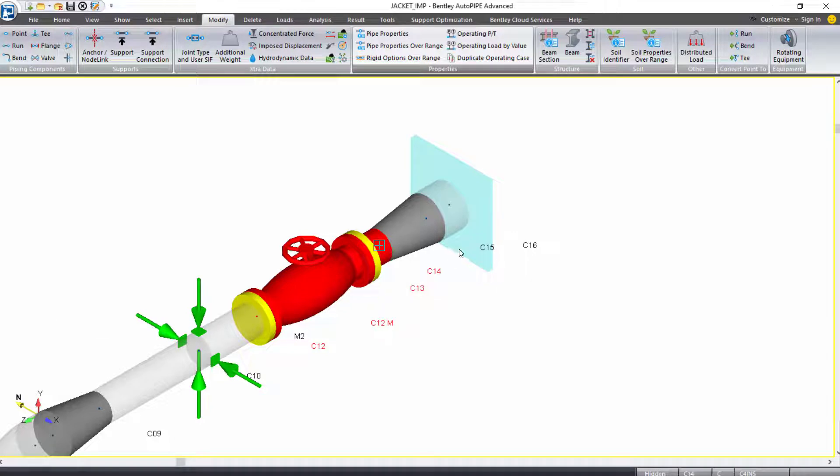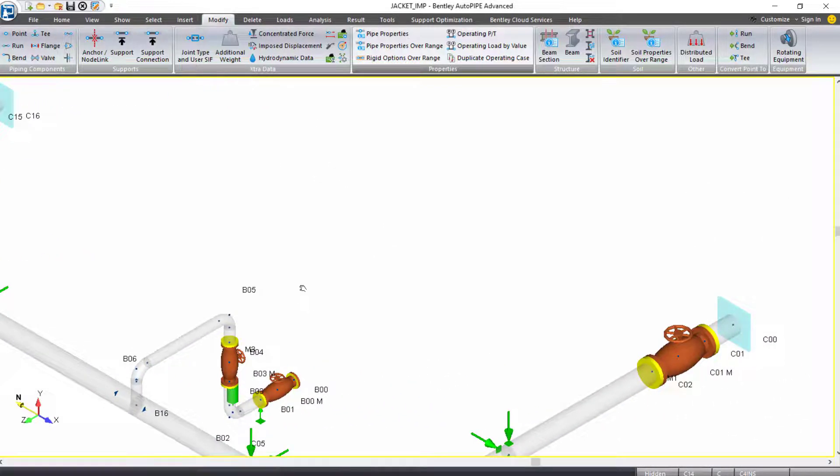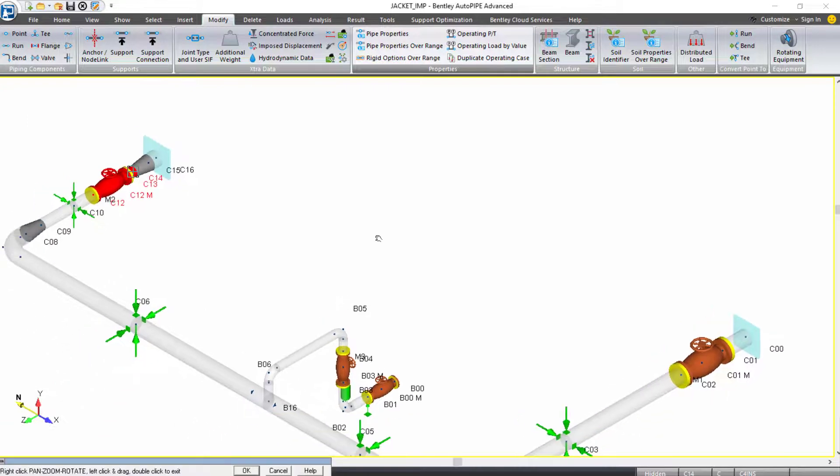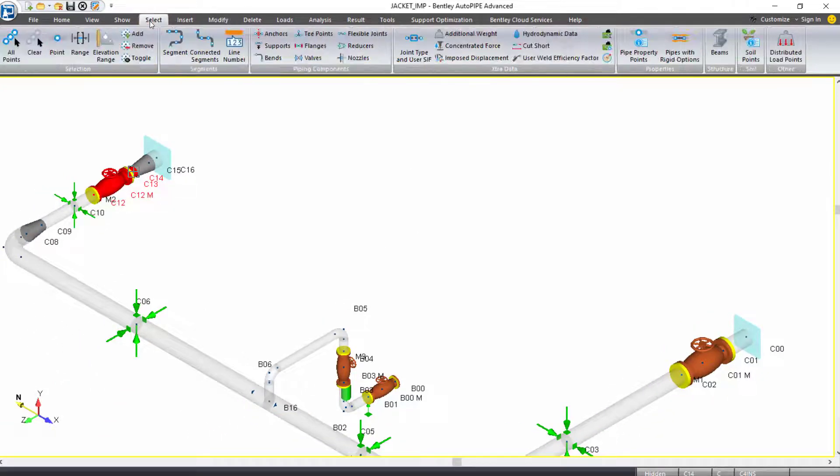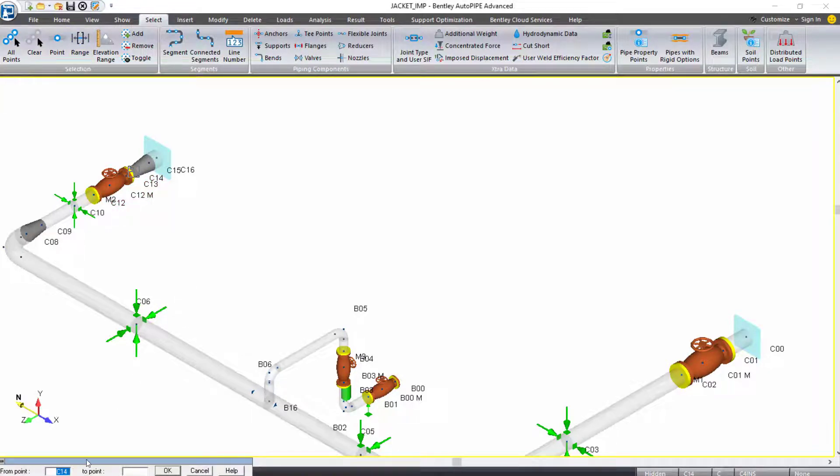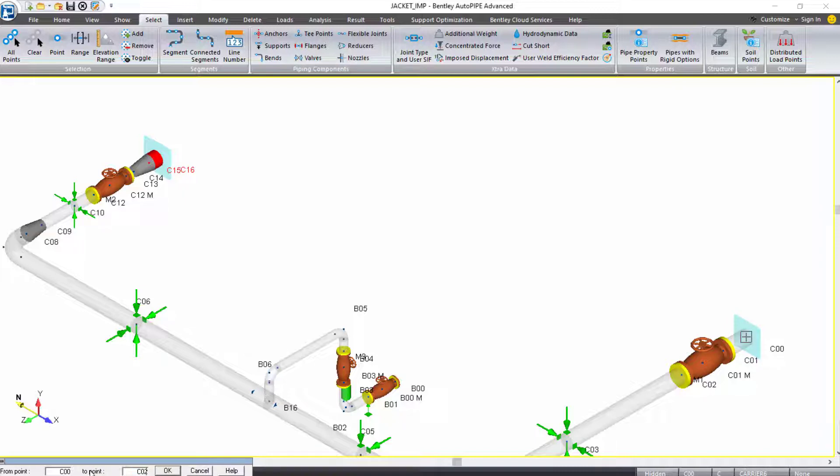Next, I'll select my six inch section of piping, which is C15 to C16, but also on this side, C0 to C2. So I have two ranges to select. On my select ribbon tab, the first thing I want to do is clear my selection, and then I'll come back to select range. I want to type in from point C15 to point C16, and I'll press tab to make that selection. Notice you don't have to select the reducer. When you select the two different sides of the reducer, it automatically then will apply to the reducer. I also want to make my second selection, from point C00 to point C02. If I tab off, that selection is made. Those are my two six inch carrier pipes outside of the jacket, so I can click OK in the command line.